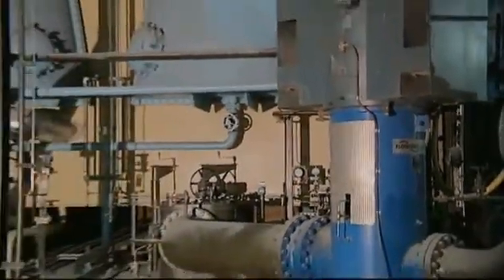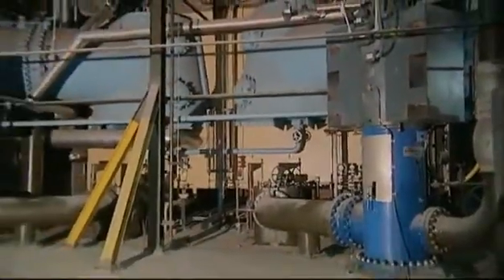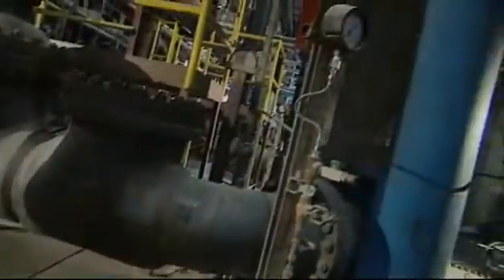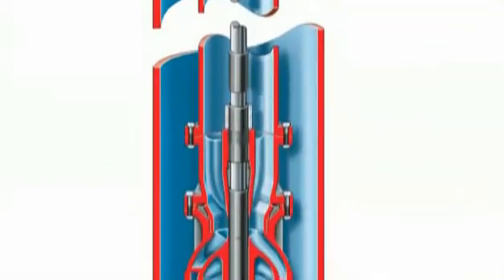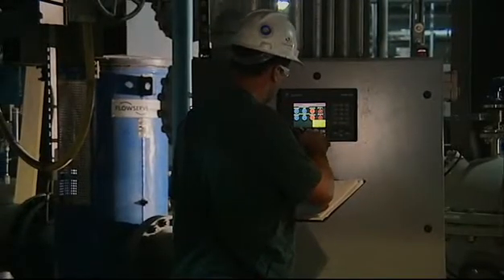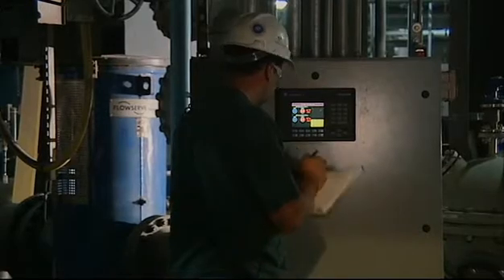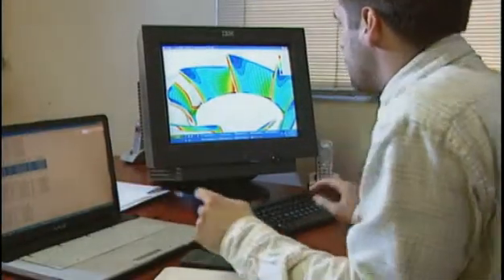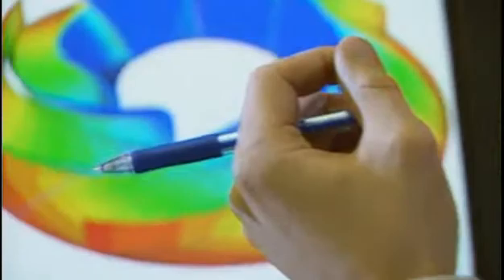Condensate. Capturing hot condensate to reuse as boiler feed water is essential to increasing plant efficiency and controlling water costs. Due to the near vacuum suction conditions, condensate pumps must meet low NPSH requirements to prevent cavitation and its detrimental effects on pump performance and reliability. For this service, FlowServe offers several heavy-duty multi-stage mixed-flow pumps, available with single or double suction first-stage impellers. These canned vertical pumps are designed for continuous operation at high flows and high pressures to ensure process uptime. FlowServe engineers around the world utilize computational fluid dynamics and flow visualization techniques to develop the world's most cavitation-resistant hydraulics, while still delivering the required performance for this critical application.